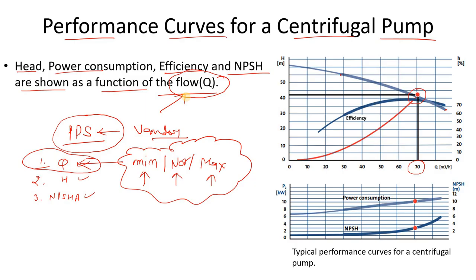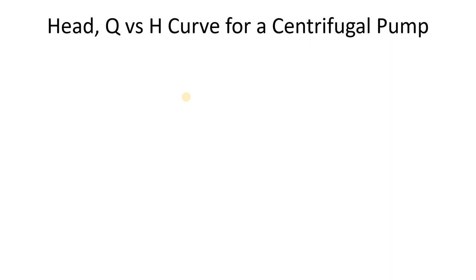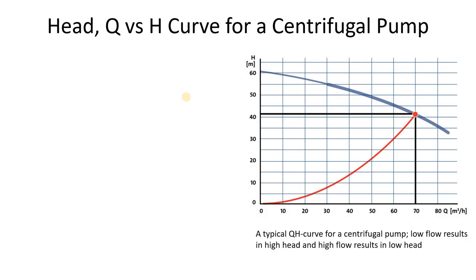When you select the right flow rate, that is the first step toward selecting the right pump. Now let's discuss the first performance curve: the head versus flow rate curve, also called the H-Q curve. From this picture you can see the Q versus H curve for a centrifugal pump. There is the BEP — the best efficiency point. At a normal flow rate of 70 cubic meters per hour, the head is approximately 42 meters.